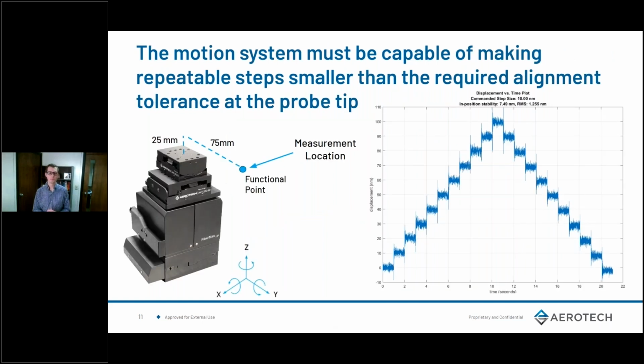Now, of course, you want to prove that your system can achieve those step sizes, and that's what we're showing here. So your automation supplier should be able to prove that either through data or estimates of their performance. What you see on the left side is that same stack. Our functional point, or your probe tip, is about 1 inch up and 3 inches out from the mounting position. And we physically measured this at that functional point, or at your probe tip location, using cap probes.